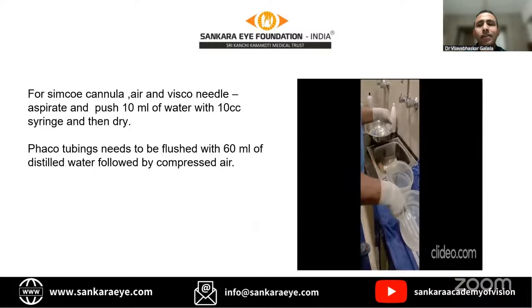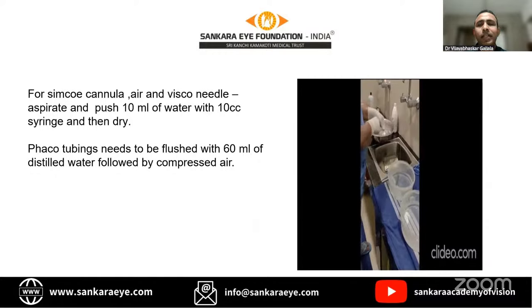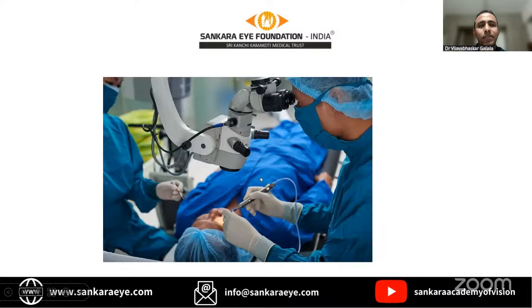So for the Simcoe cannula, you can use a 10 cc syringe. You can flush it multiple times. When you are flushing, make sure that the effluent goes to a separate bin or sink, and avoid splashing this effluent on surrounding structures. And when you are using the phaco tubings, which are longer, this 10 cc syringe is not sufficient. You can use a 60 ml syringe, or 60 ml distilled water should be flowed through these phaco tubings, followed by compressed air for better cleaning of the inner surface of these tubes.